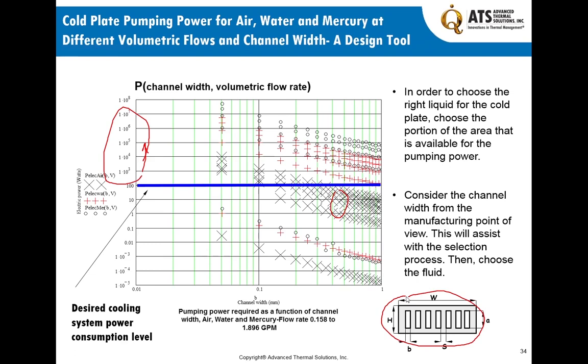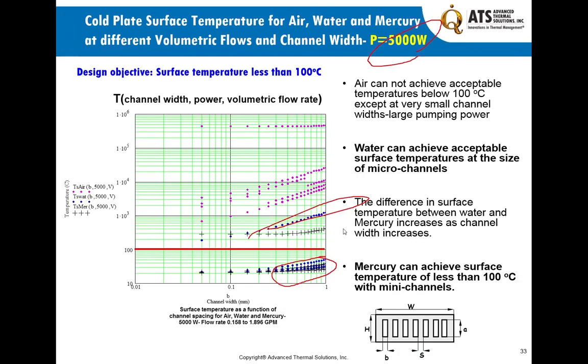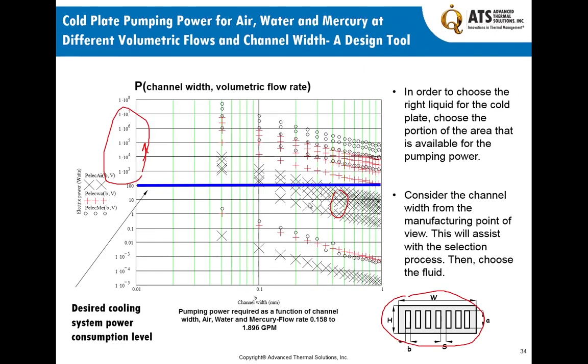A simple analytical model, before we jump into CFD, provides significant design guidance. With simple parametric analyses you can develop charts for your specific application to see where you land on your cold plate design. The basic equations have been in the literature for many decades. And as we'll see, there is very good agreement between the analytical modeling and CFD modeling. However, throughout all of this, we've made the assumption that power is uniformly distributed over the surface.